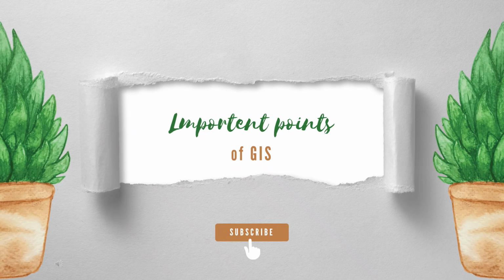Important points. 1. Continuous bus lengths without gas segregation shall not be provided. 2. Each section shall be provided with necessary valves for evacuation and refill of gas without evacuation of any other section. 3. Each gas compartment shall be provided with temperature compensated gas density switch for gas monitoring and maintenance. 4. Pressure relief devices shall be provided in the gas sections to protect the main gas enclosures from damage or distortion during the occurrence of abnormal pressure increase or shock waves generated by internal electrical fault arcs. Rupture diaphragms with suitable deflectors shall be provided to prevent uncontrolled bursting pressures developing within the enclosures under worst operating conditions.